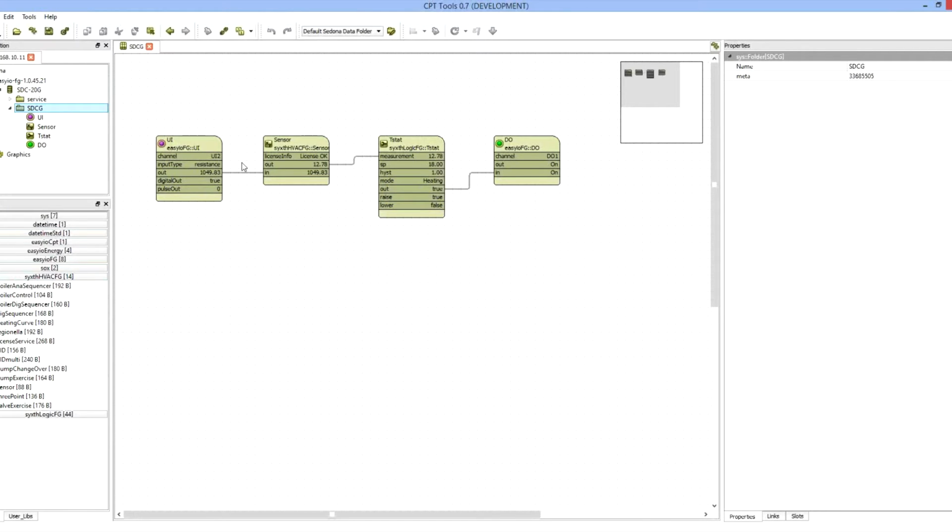Now, if we wanted to back up that application from the controller, remember that with the Sedona controllers we always program online. So we connect into the controller with the tool, but we are actually looking into the controller. So it is a view of the controller. When we program, we do it online in the RAM memory, and when we make any changes, there's a little asterisk on the top side, and that reminds us that we have to save the application in the controller to non-volatile memory, and we can do that by pressing save application.